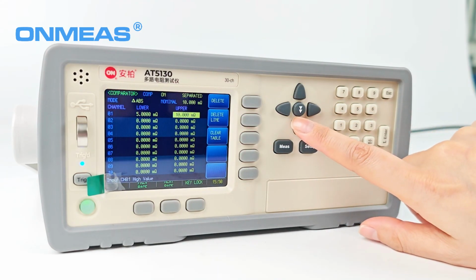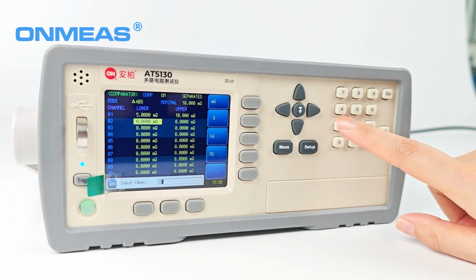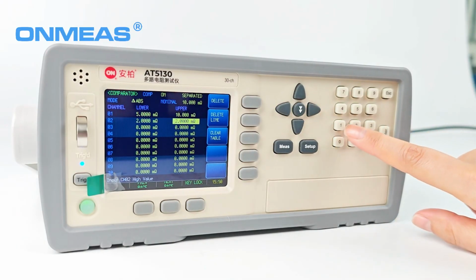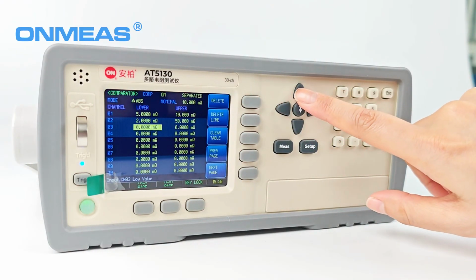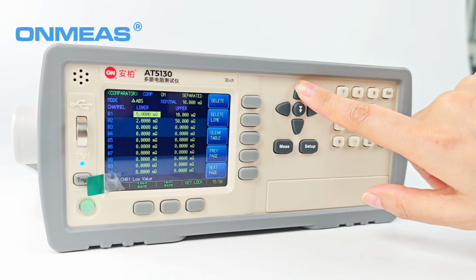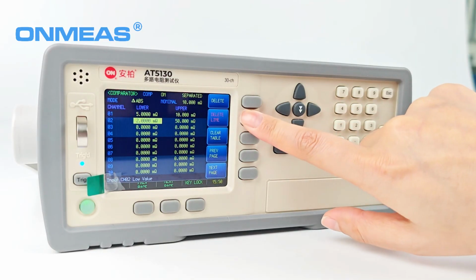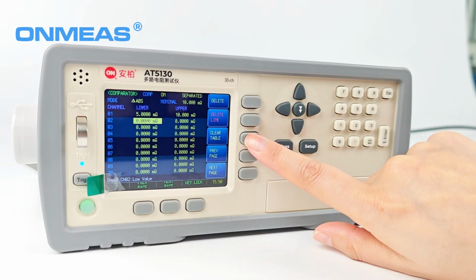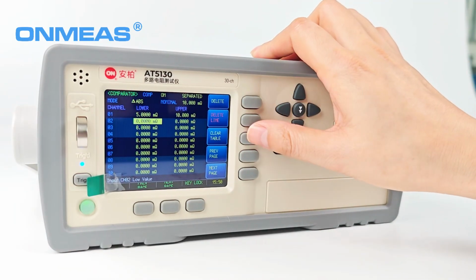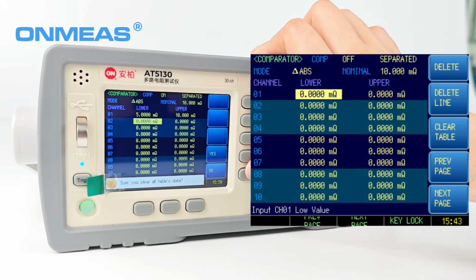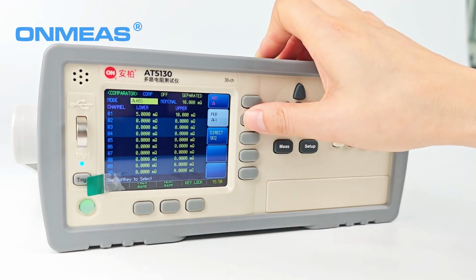On the comparator page, you can set the following items: comparator switch and input mode for comparator gears, comparison method settings, nominal value settings, as well as the upper limit and lower limit data input for each gear. The upper and lower limit values can be deleted individually or in batches using the function keys. The gear setting method can be either uniform or individually selectable.